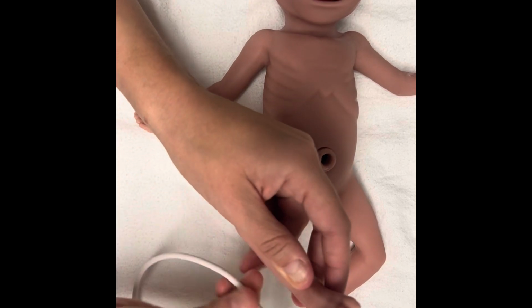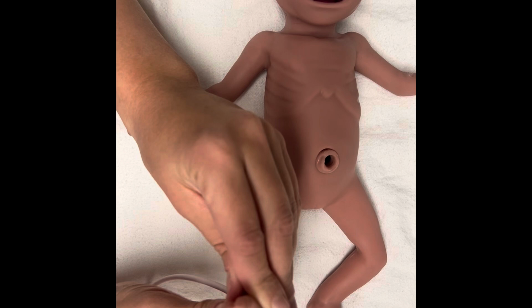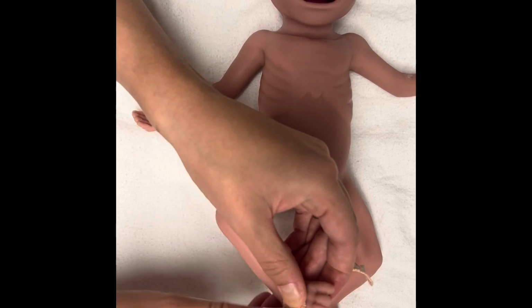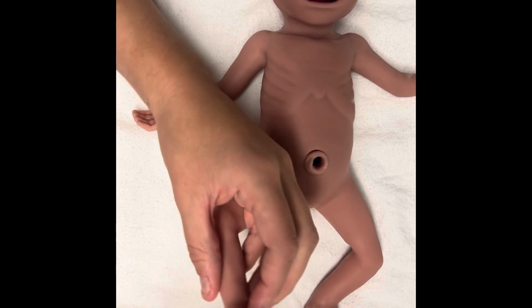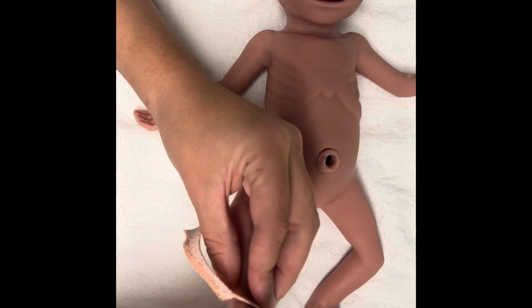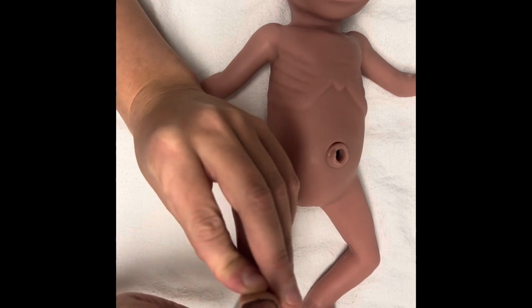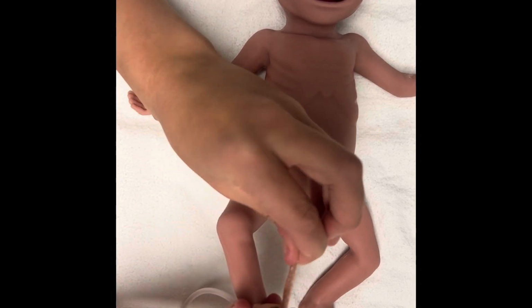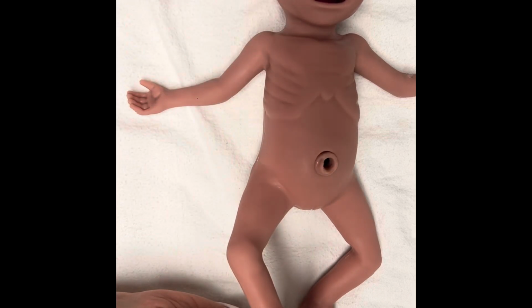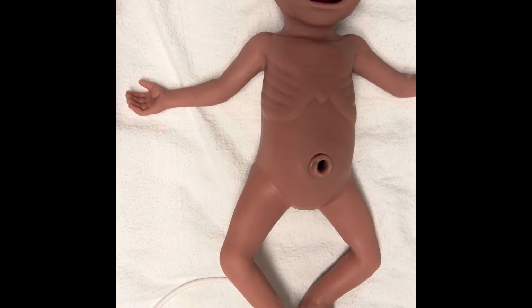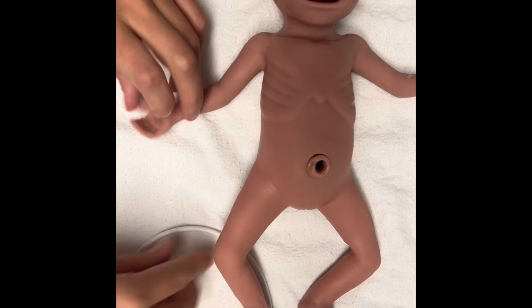and that's going to give me a better reading, so that's also acceptable. And then when we go down to the feet, again, I just want to apply it at a thin part of the foot so that both sides can communicate with each other, the light and the sensor, and I can achieve that on either side. So those are all of my options and a quick way to troubleshoot my saturation probe.